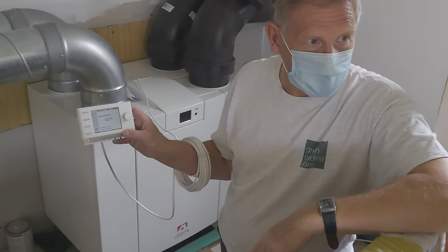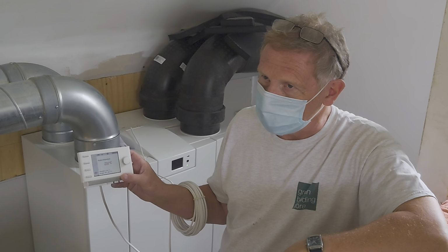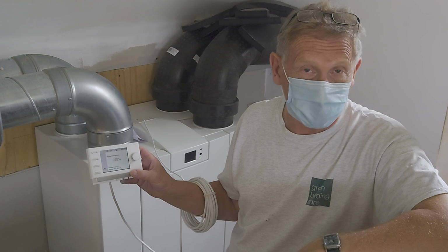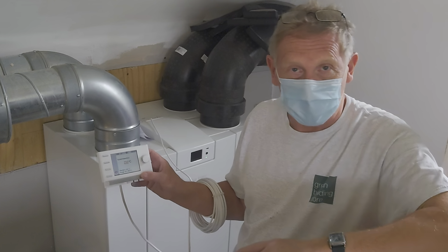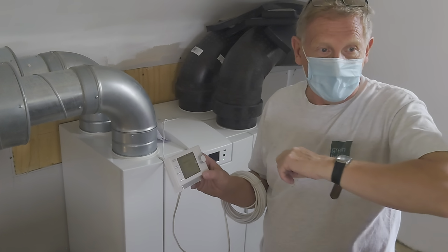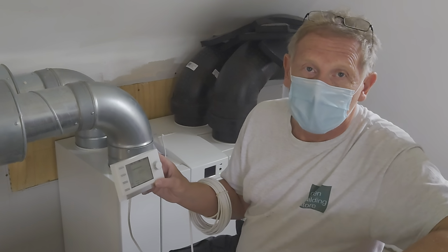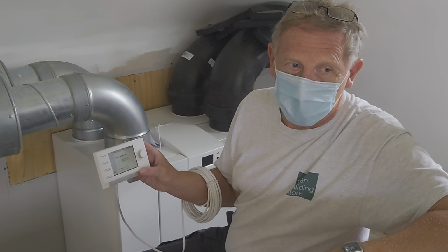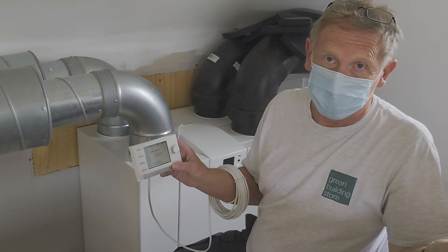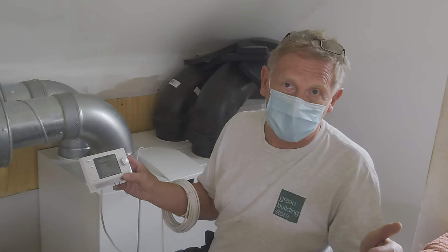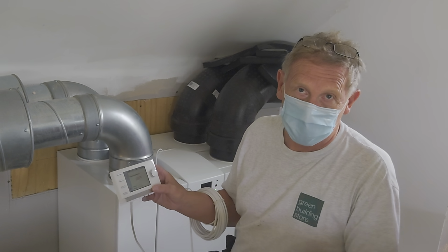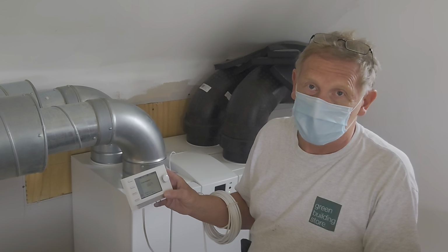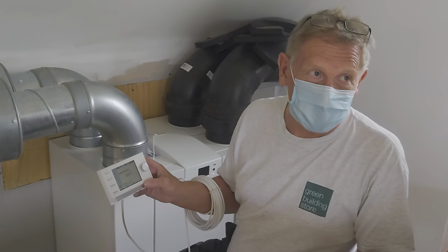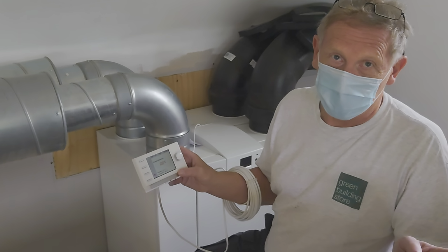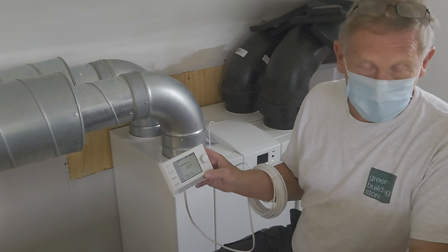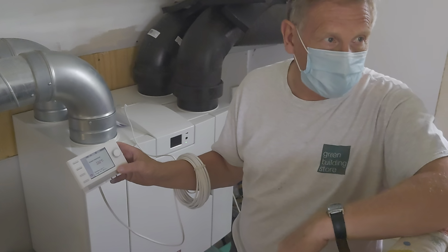Also, that's registering at the top of every room, isn't it? Well, actually, the machine thinks that your average house temperature is the average of all of your extract rooms, because the temperature sensor is on the extract side of the machine. So if you have one cool, unheated room, like a spare bedroom, it might cool down the average temperature. For example, the extract air from the kitchen could be, say, 25 degrees. The extract air from your bathroom, toilet and utility, which don't have any south-facing windows, could be 21 degrees. So the air going into the machine is going to be the average of those. It might be 25 up here, but the average going to the machine might be 22, 23 if your other extract rooms are much cooler, or if you've got a window open somewhere.